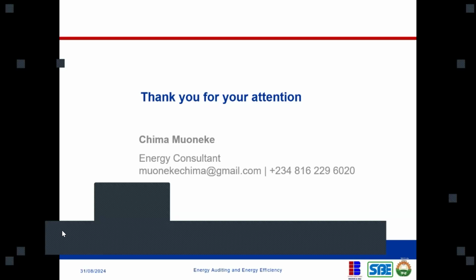You asked about the voltage imbalance and whether it affects the functionality of the generator. The effect is felt more on the consumption side, on the cables. We have wires connected from the generator to the equipment. If you have excess consumption or excess power connected to one of the phases, it can lead to a fire outbreak because there's going to be high demand on that phase, whereas the other phases might not be loaded as much as they should. So it has more impact on the wires and on the load. If you're connected to a three-phase load, it impacts that load more. It also has impact on the functionality of the generator, but it's more on the cables and the load.